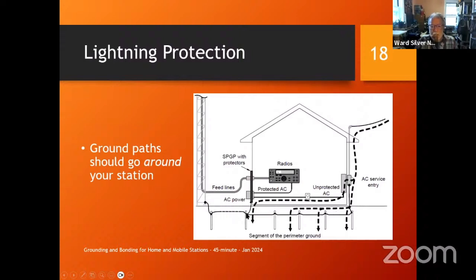Multiple ground rods. If your tower is close to the house, say 50 feet or less, you want to bond that up there too. And so here comes the lightning surge. This time it hit the power lines, which is quite common. Comes in, says, oh, look, I've got this really nice perimeter ground system. A lot of heavy direct paths to the earth.